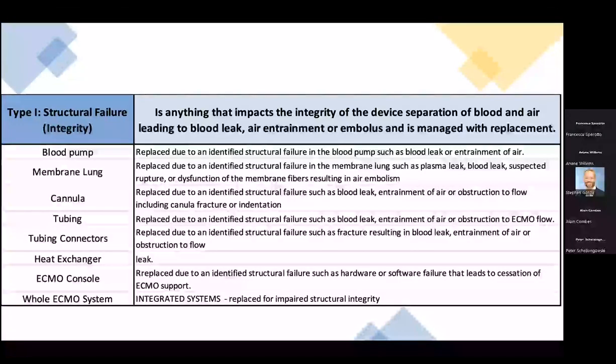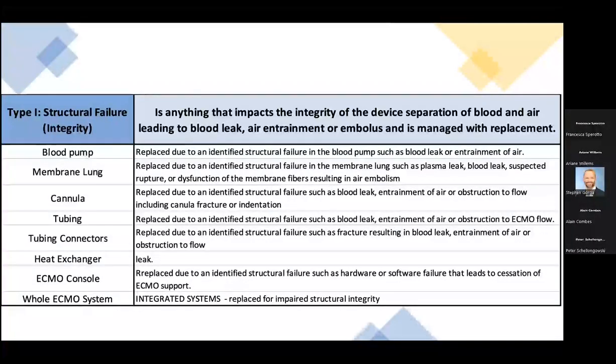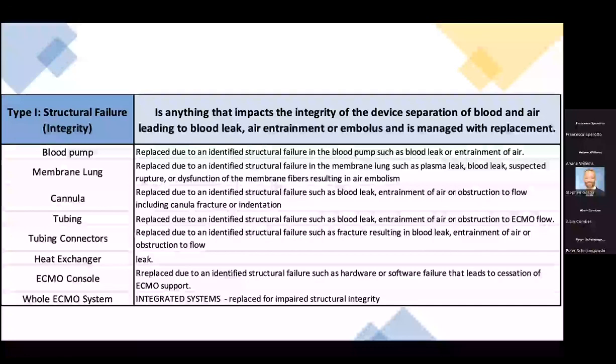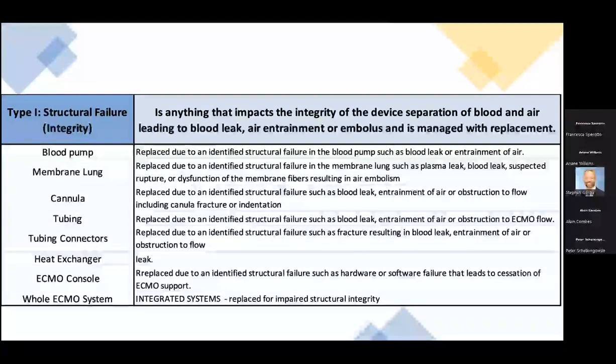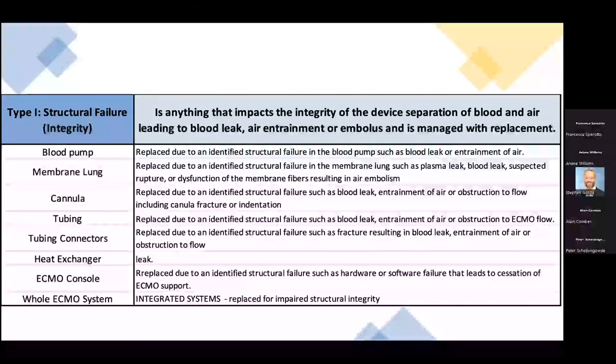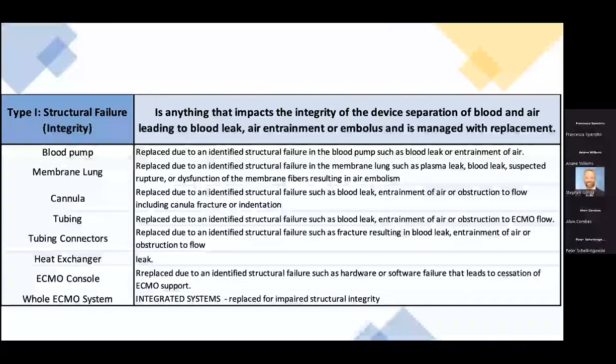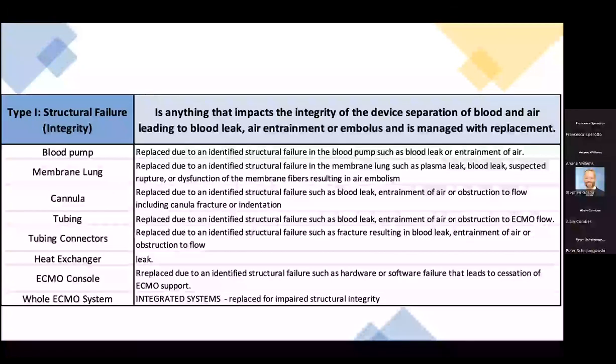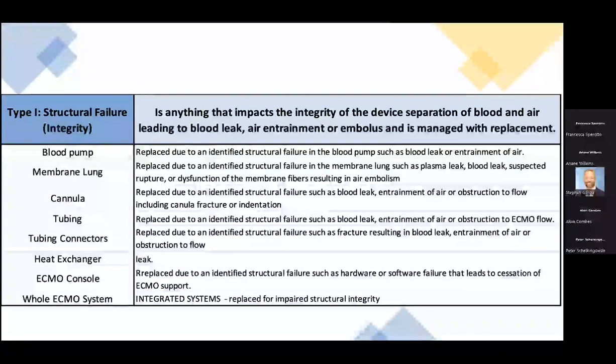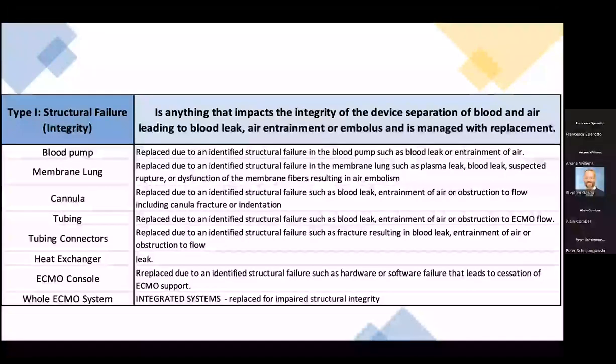A cannula failure was defined as a replacement due to identified structural failures such as blood leak, entrainment of air, or obstruction to flow, including cannula fracture or indentation. Then we include the tubing, so it's replaced due to identified structural failures such as blood leak, entrainment of air, or obstruction to ECMO flow. Tubing connectors is a failure that requires a replacement due to identified structural failure such as fracture resulting in blood leak, entrainment of air, or obstruction of flow.